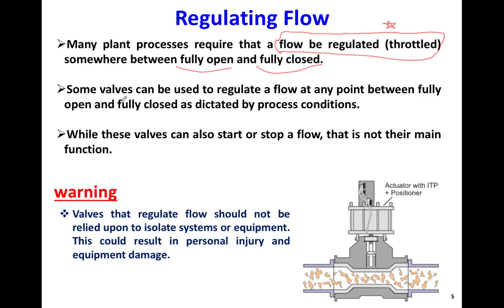We use regulating valves to adjust the flow rate between the fully open and fully closed extremes. Some valves are only used for fully open and fully closed conditions, while others can work at any point between fully open and fully closed. Valves used for regulating, adjusting, or throttling flow are not really designed for stopping or starting the flow — stopping and starting needs its own specific valve. The main function of a regulating valve is really for adjusting the flow rate.